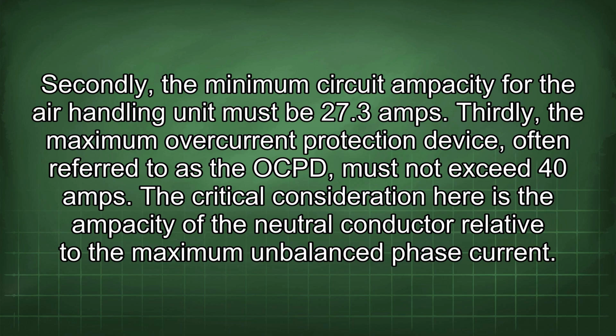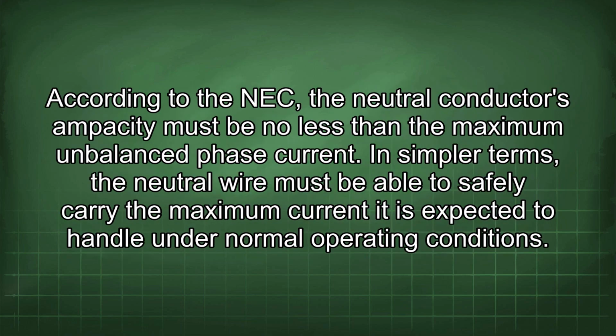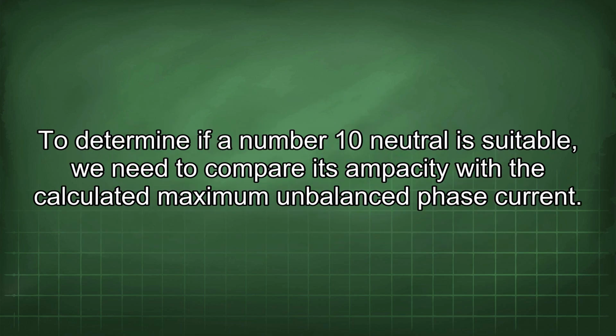The critical consideration here is the ampacity of the neutral conductor relative to the maximum unbalanced phase current. According to the NEC, the neutral conductor's ampacity must be no less than the maximum unbalanced phase current. In simpler terms, the neutral wire must be able to safely carry the maximum current it is expected to handle under normal operating conditions. To determine if a number 10 neutral is suitable, we need to compare its ampacity with the calculated maximum unbalanced phase current.